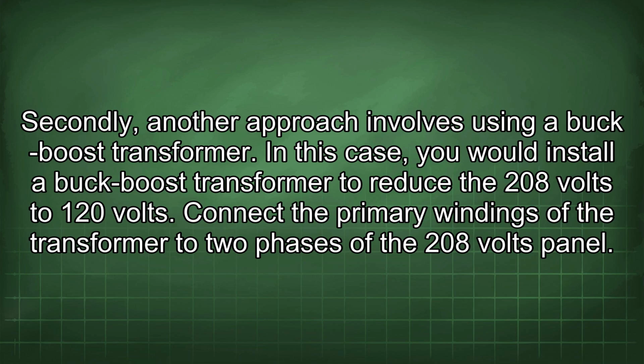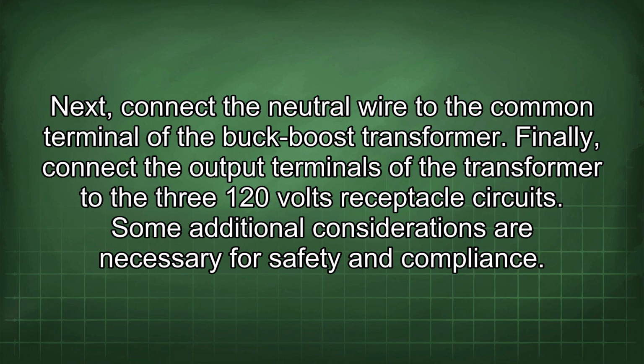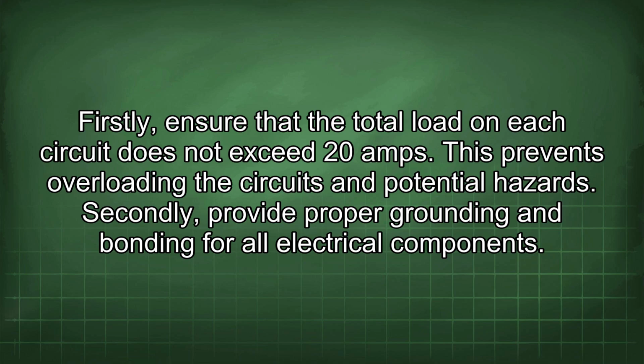Connect the primary windings of the transformer to two phases of the 208 volts panel. Next, connect the neutral wire to the common terminal of the buck-boost transformer. Finally, connect the output terminals of the transformer to the three 120 volts receptacle circuits. Some additional considerations are necessary for safety and compliance. Firstly, ensure that the total load on each circuit does not exceed 20 amps.